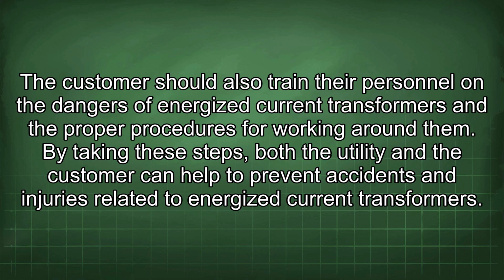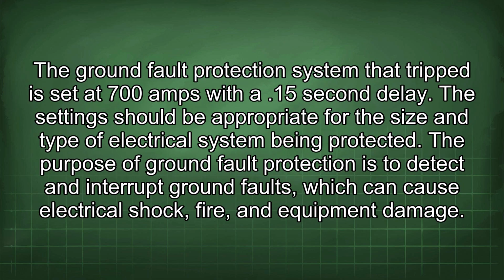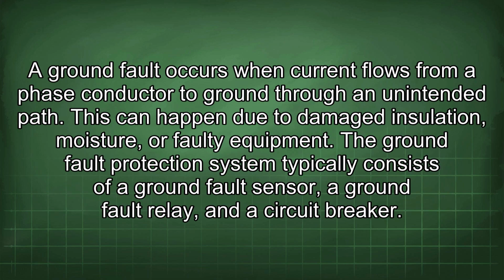By taking these steps, both the utility and the customer can help to prevent accidents and injuries related to energized current transformers. The ground fault protection system that tripped is set at 700 amps with a .15 second delay. The settings should be appropriate for the size and type of electrical system being protected. The purpose of ground fault protection is to detect and interrupt ground faults, which can cause electrical shock, fire, and equipment damage. A ground fault occurs when current flows from a phase conductor to ground through an unintended path. This can happen due to damaged insulation, moisture, or faulty equipment.